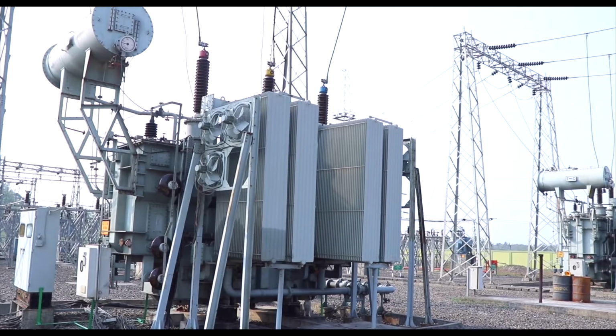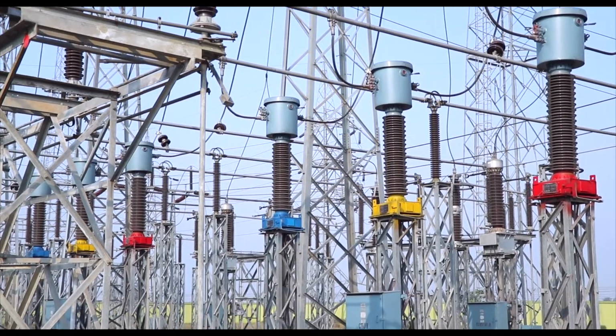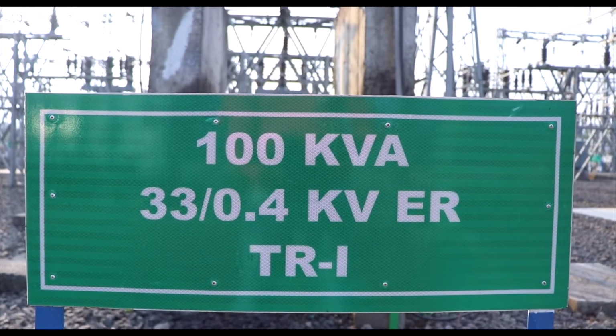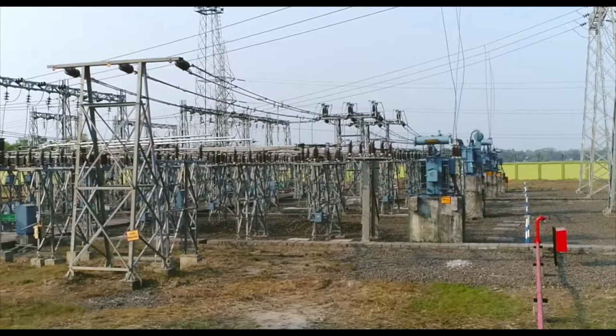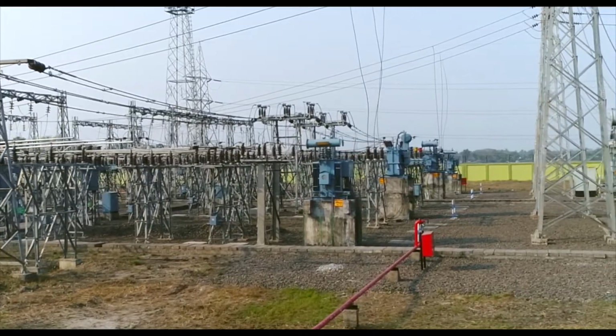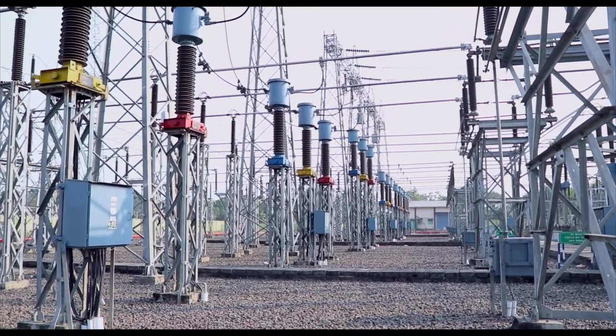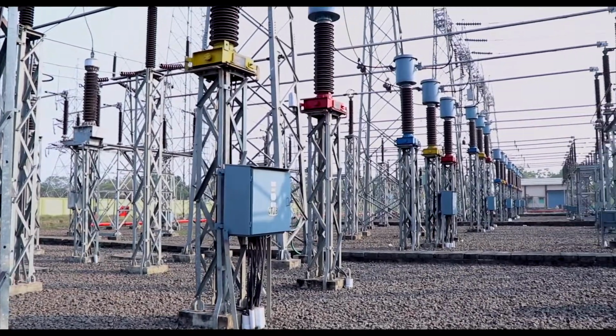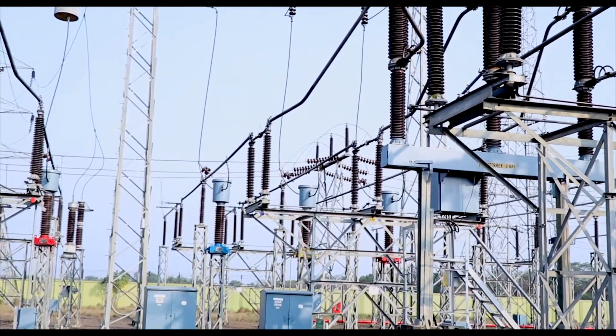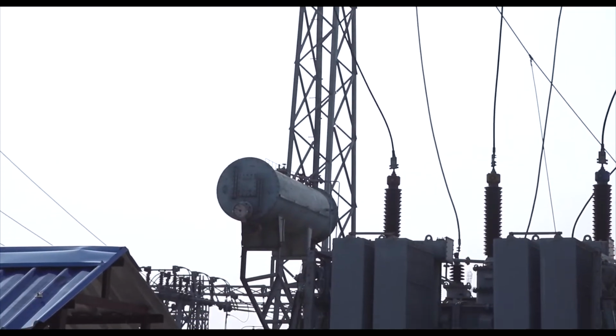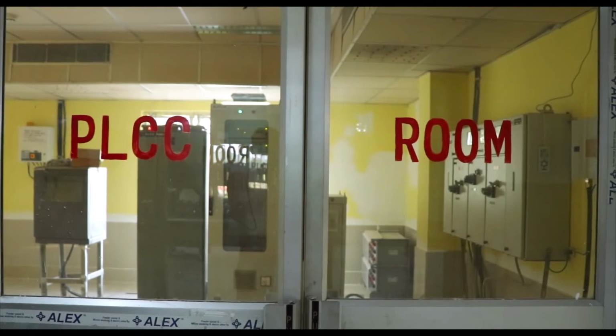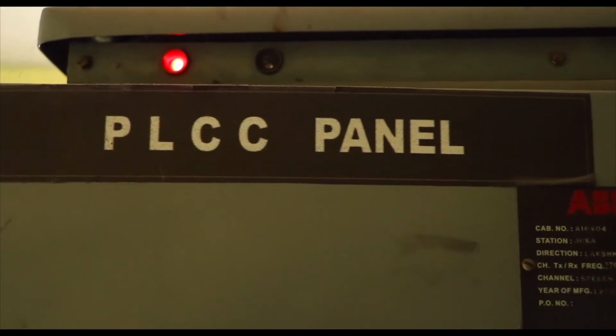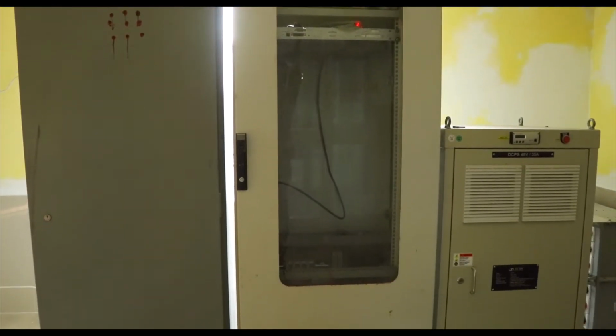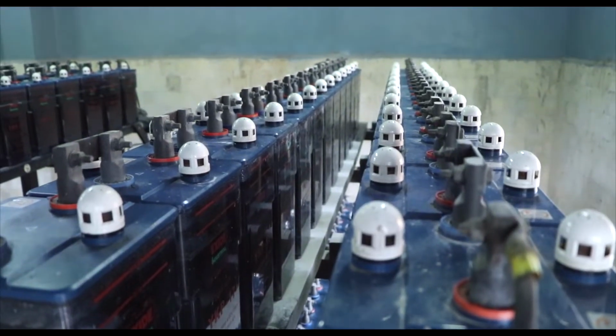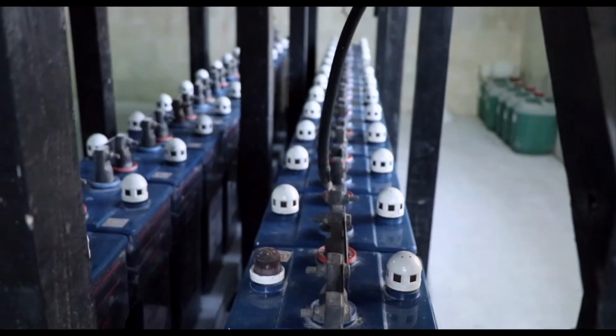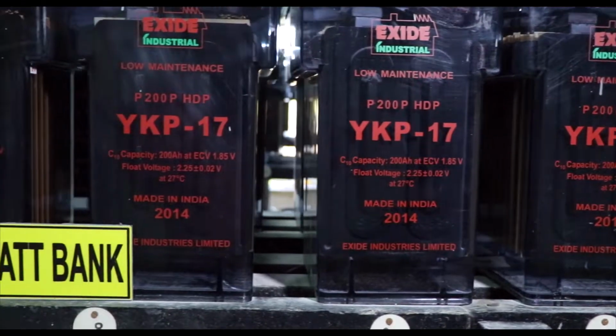This substation has two 100 kVA earthing transformers and two 315 kVA 33 by 0.415 kV station transformers to cater to auxiliary load through ACDB. Installed with two L&T make 415 volt ACBs with bus coupler for 132 kV and 33 kV. 220 volt DC circuits are powered by a 220 volt charger via DCDB, and communications like PLCC point-to-point connection by a 48 volt charger via 48 volt DCDB, with a well-maintained backup battery bank of 107 and 24 cells respectively. The total illumination is controlled by MLDB including DC emergency light.